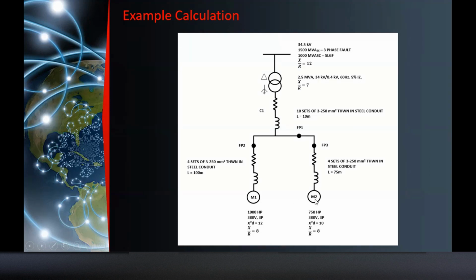So I have two motors connected, 1000 horsepower, 380 volts, subtransient of 12. This is the reactance during the half cycle I mentioned earlier, and X over R of 8. Then we have 750 horsepower, 380 volts, subtransient of 10, and X over R of 8. So the problem here: what is the fault current at fault point 1, to size up the breaker here? And what is the fault current at fault point 2, to size up the breaker here as well as the circuit breaker here?